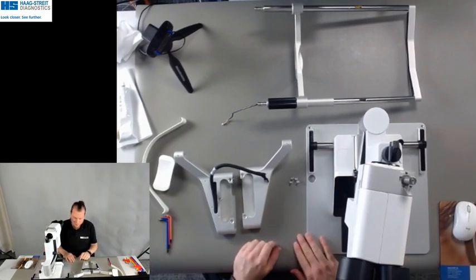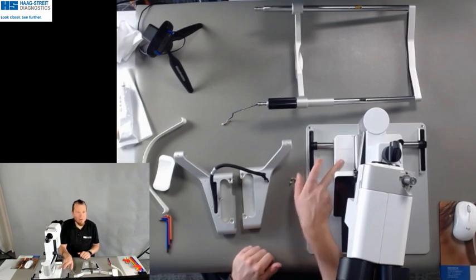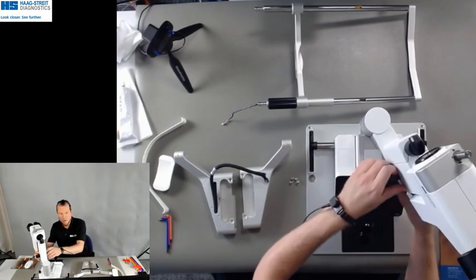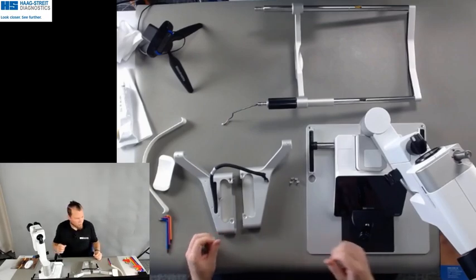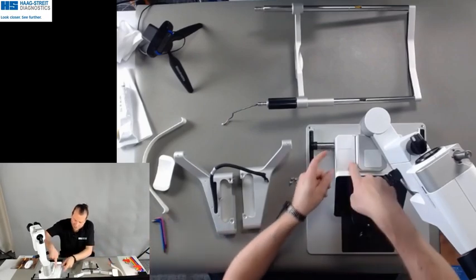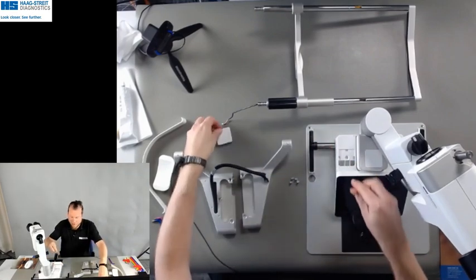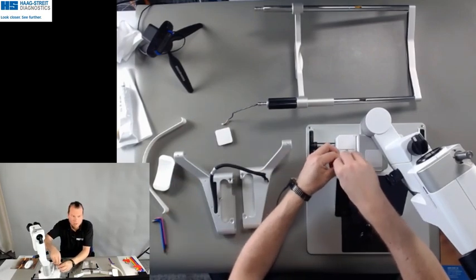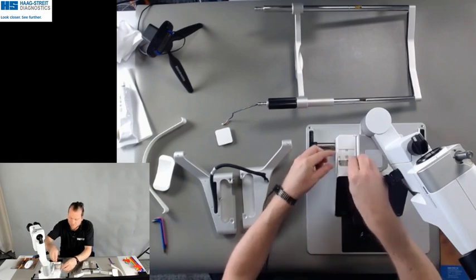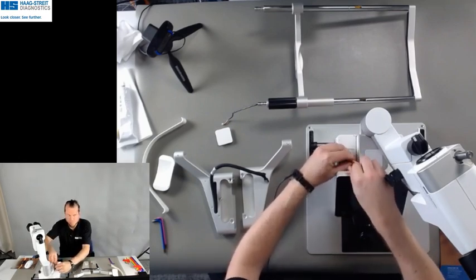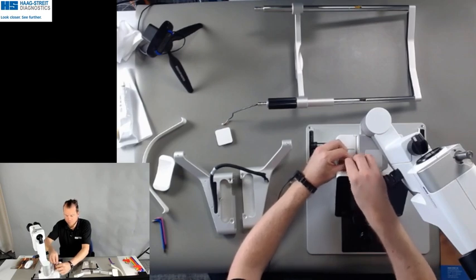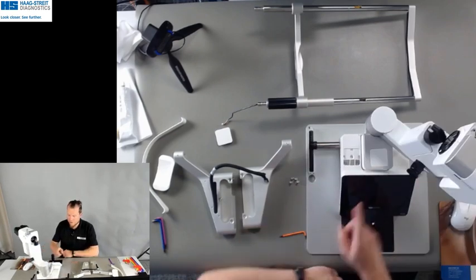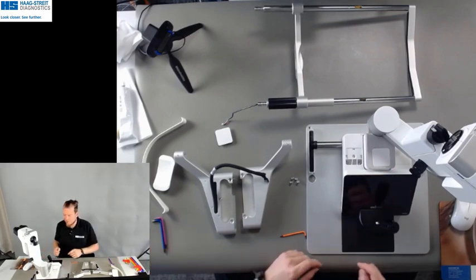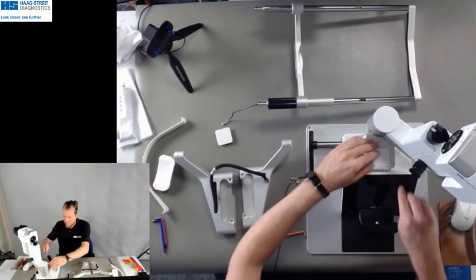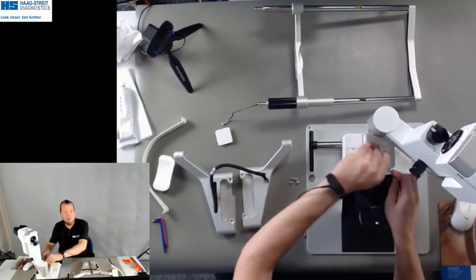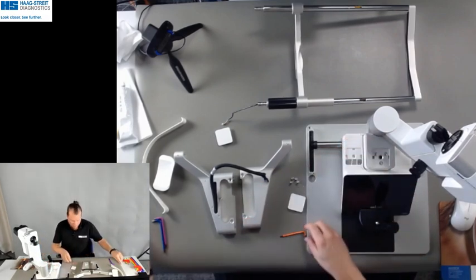Then we need to remove the cover here on the side. Turn over the tower and the microscope. Then we take a Torx number 10. You can remove this cover here, unscrew the 2 screws inside of here. Then we need to remove this cover here. In later versions, you will just be able to press into one corner and it pops up. With the first Elaras, you still need to use a small screwdriver or your fingernails to pop this cover out.